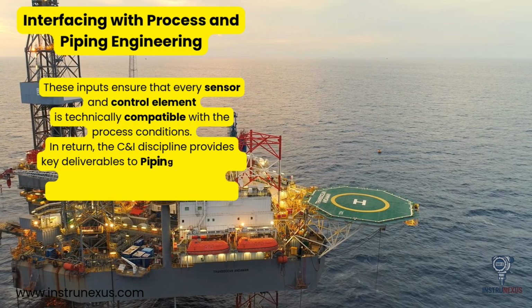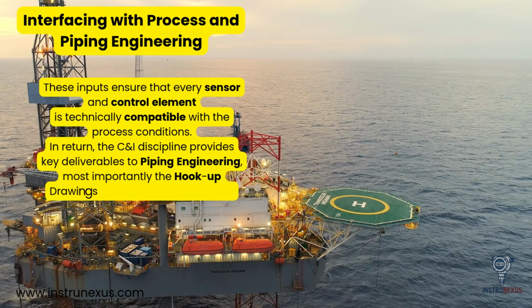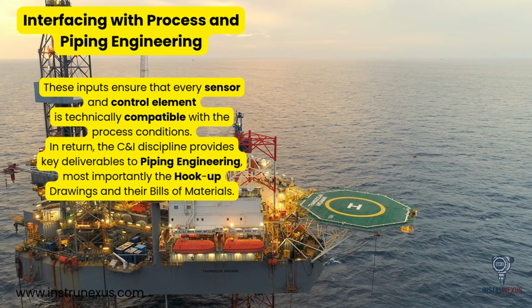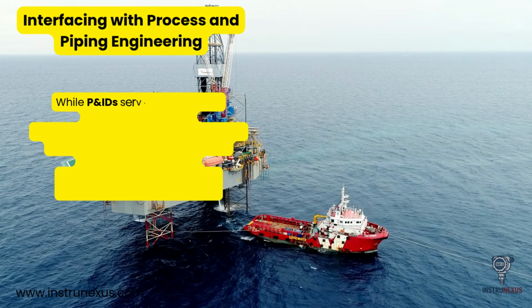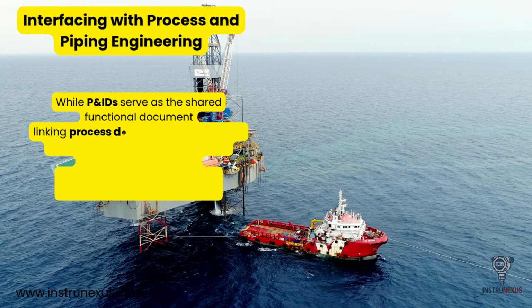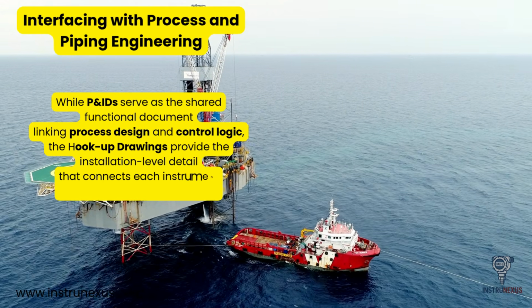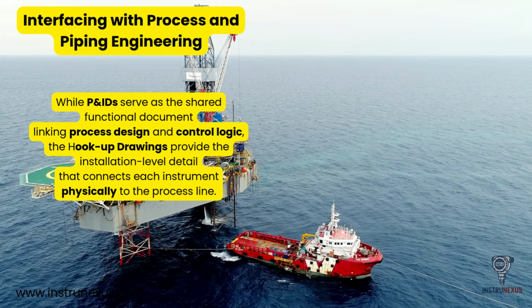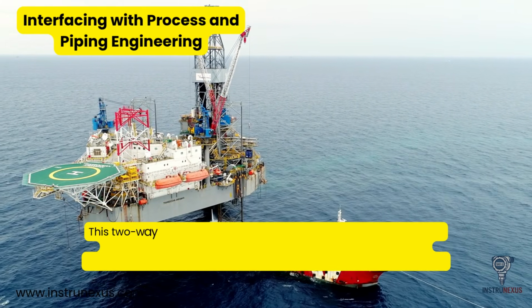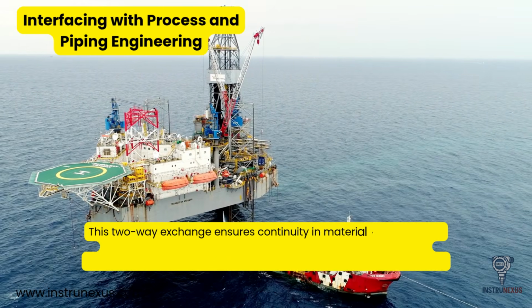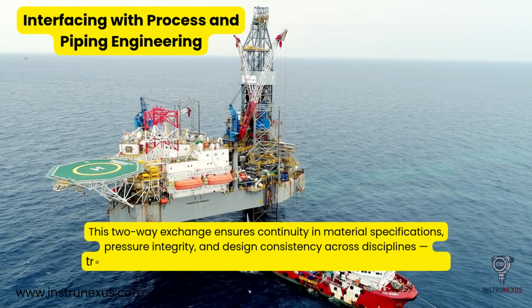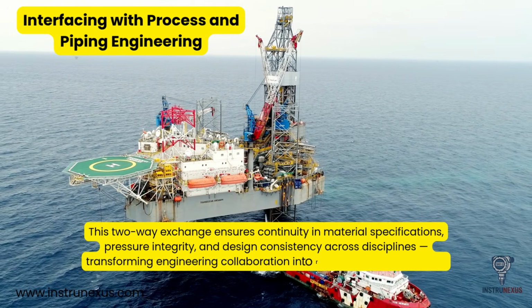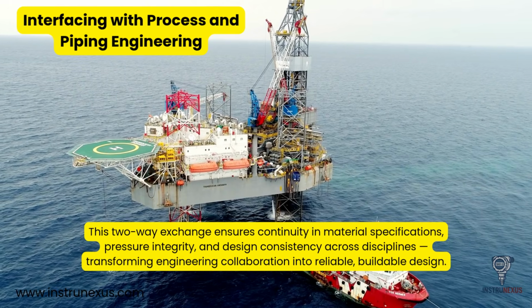In return, the C&I discipline provides key deliverables to piping engineering, most importantly, the hookup drawings and their bills of materials. While P&IDs serve as the shared functional document linking process design and control logic, the hookup drawings provide the installation-level detail that connects each instrument physically to the process line.